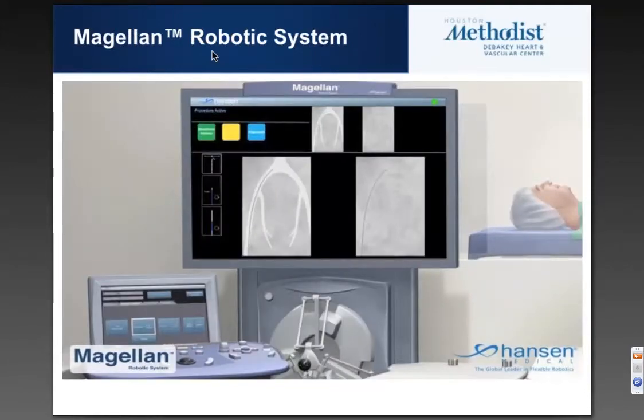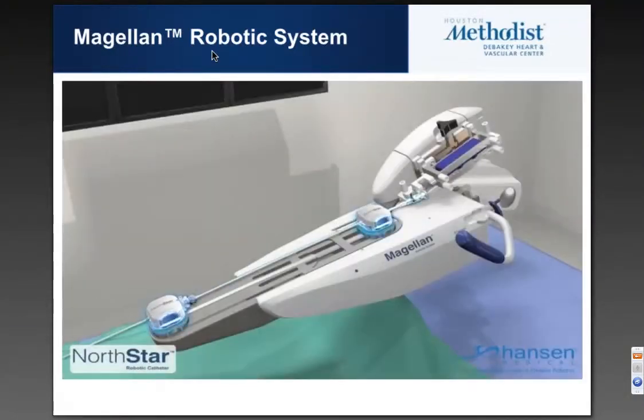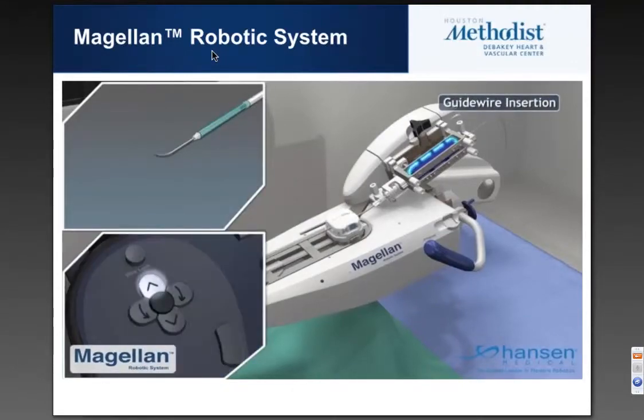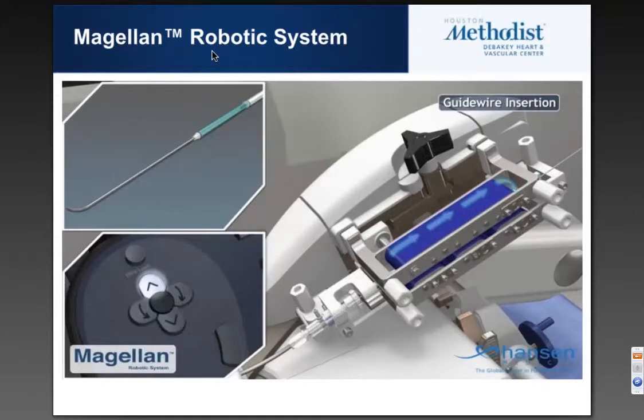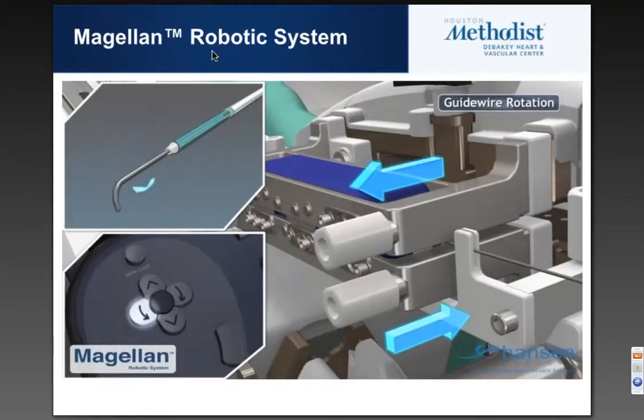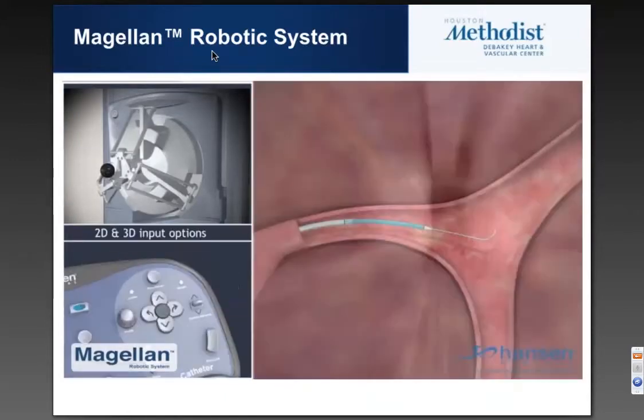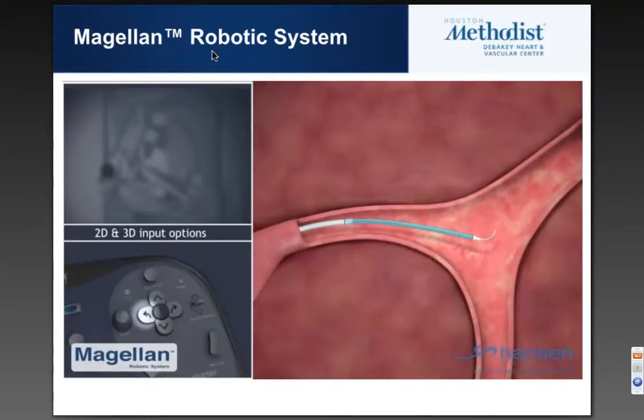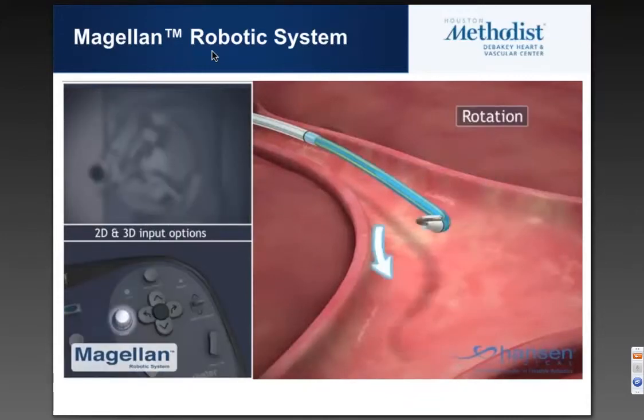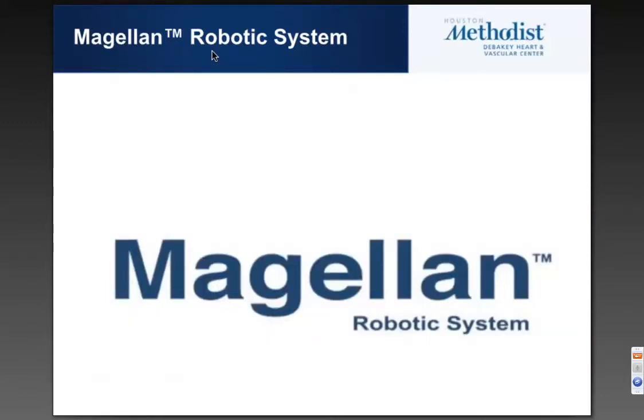This is a video going through the details of the mechanism. Here's the RCM and the catheter being loaded onto it. From the workstation you can control the guide wire, driving it and retracting it, and you can also torque it. The two belts basically run over each other and can torque that wire very much like you would do with your own fingers or a torque device. This gives you six degrees of freedom, which can be very important when you're working in this complex three-dimensional space.